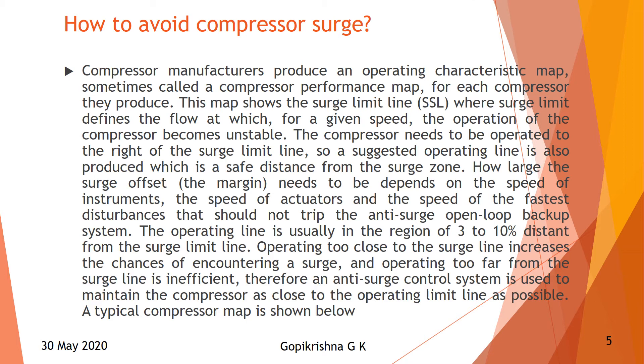How large the surge offset margin needs to be depends on the speed of the actuators and the speed of the fastest disturbance that should not trip the anti-surge backup system. The operating line is usually in the region of 3 to 10% distance from the surge limit line. Operating too close to the surge line increases the chance of encountering a surge, and operating too far from the surge line is inefficient.